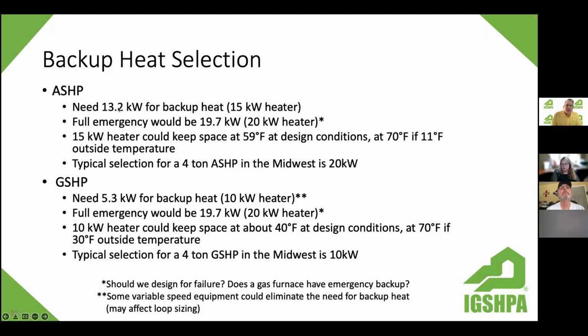We need 13.2 kW on the air source heat pump to meet the thermostat needs, okay? So that would be a 15 kW heater for all practical purposes; we probably couldn't buy a 13.2, I don't believe. Our full emergency heat, if we wanted to plan for failure, which you always have to ask yourself, does a gas furnace have full emergency backup? So that's kind of a judgment call there. You'd have to go with 20 kW if you wanted to have the full backup.